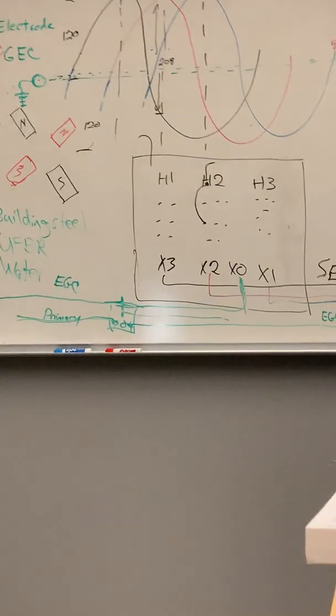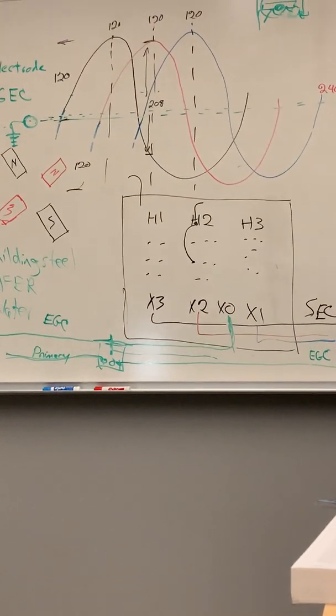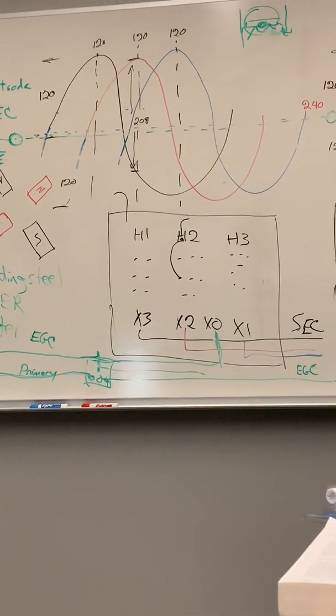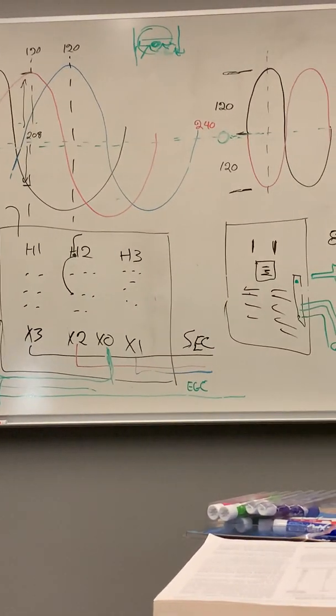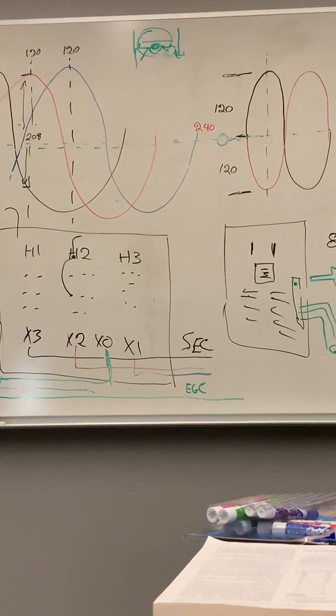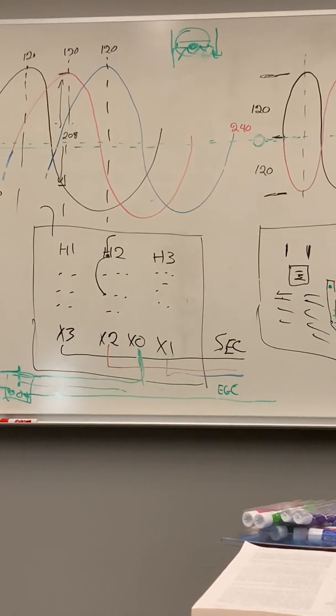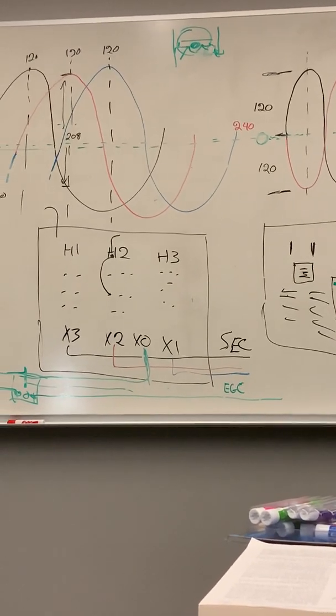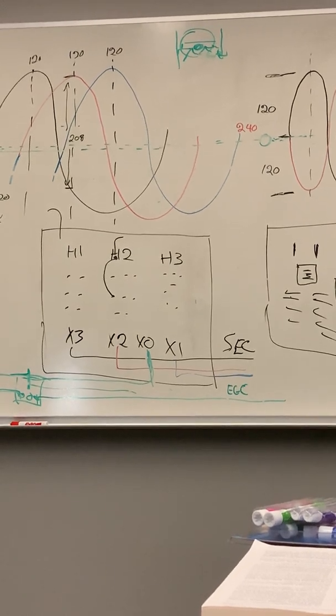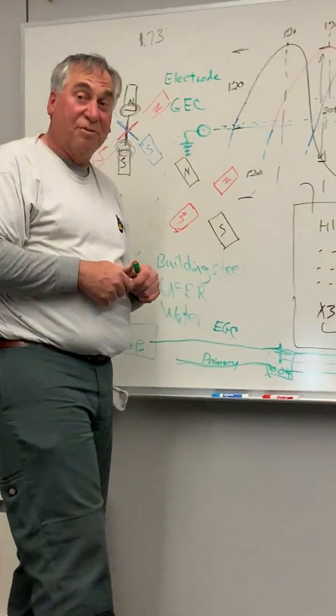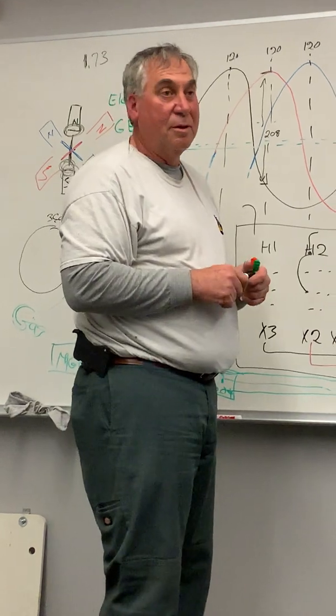Can I use only one conductor to bond all the water and the rod on the service side? Yeah, but you gotta be careful with water. You do it within the first 5 feet where it enters the building, unless they bury plastic pipe out in the street, and that doesn't help you either way. The code says first 5 feet.